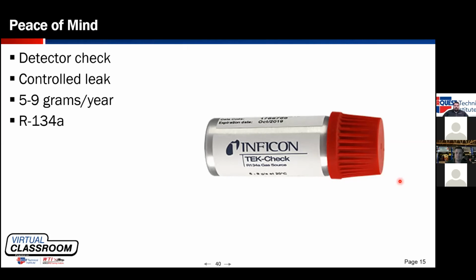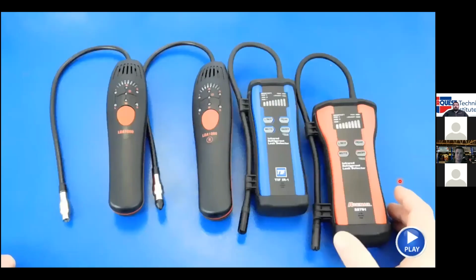So that's a good check if I want to see if my detector is working. Part of these standards for leak detectors is that the manufacturer will include documentation with the leak detector of yes or no if it false triggers on certain chemicals, and we can use that to our advantage. I'm going to skip this video of testing leak detectors because we are starting to run short on time.